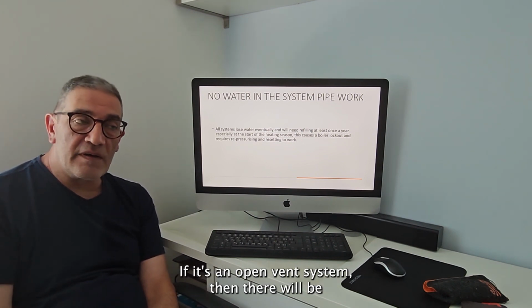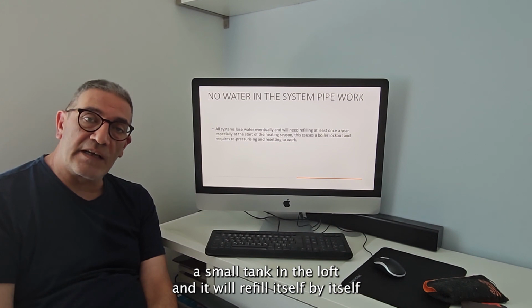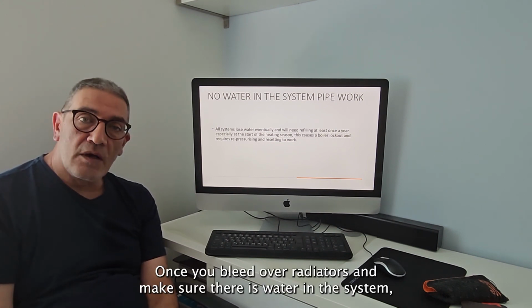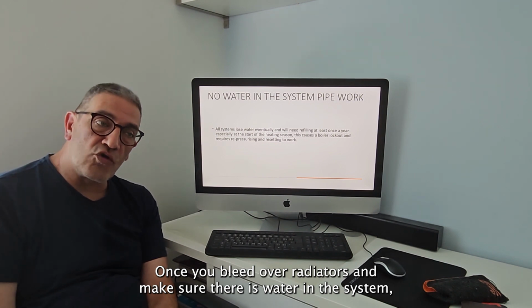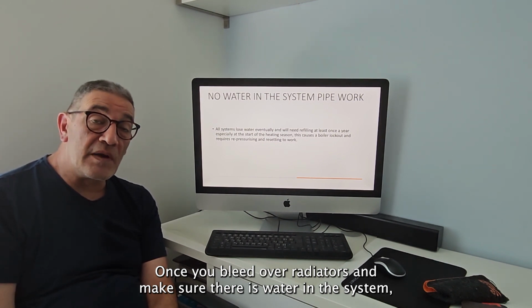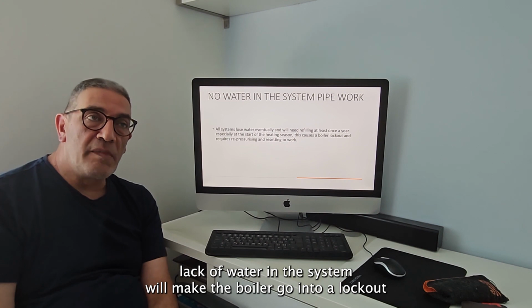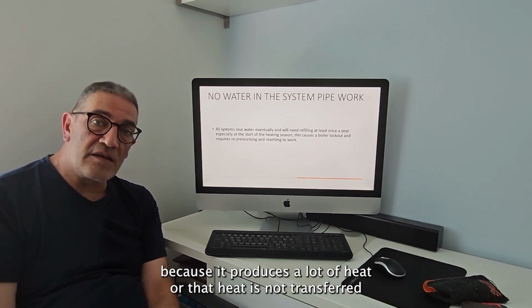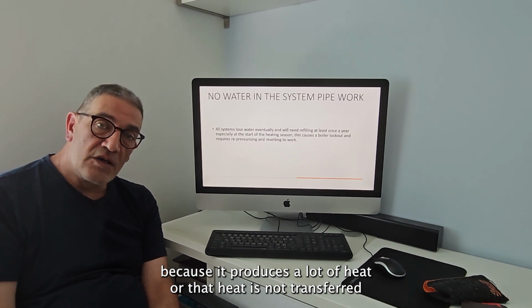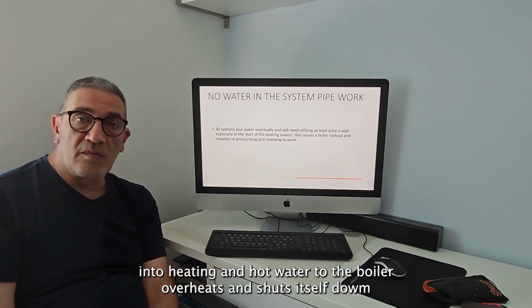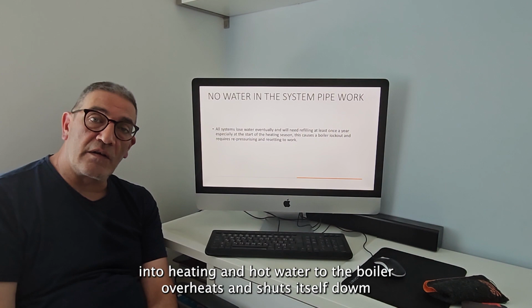If it's an open vent system, then there will be a small tank in the loft and it will refill by itself once you bleed all the radiators and make sure there is water in the system. Lack of water in the system will make the boiler go into a lockout, because it produces a lot of heat, but that heat is not transferred into heating and hot water, so the boiler overheats and shuts itself down.